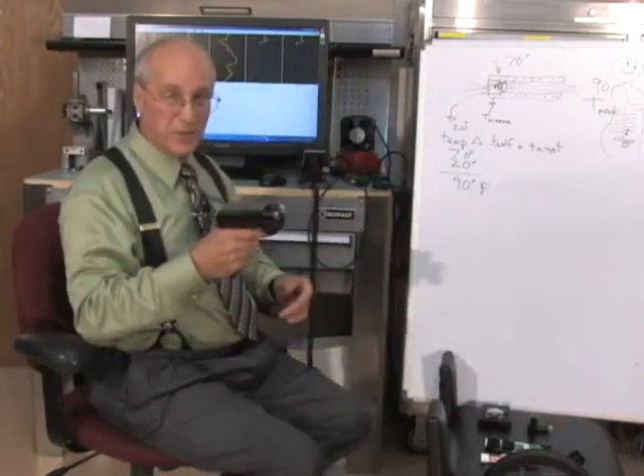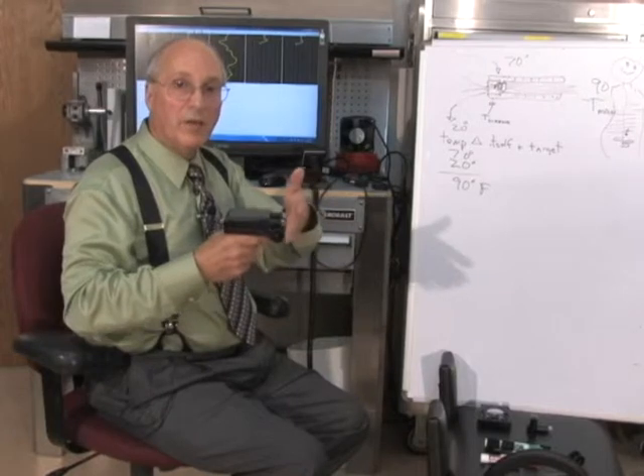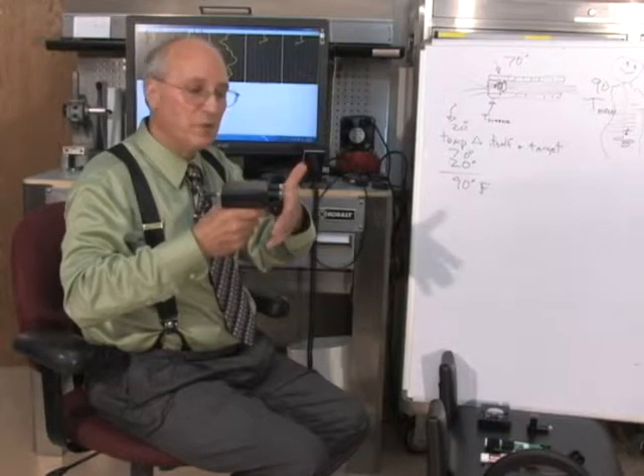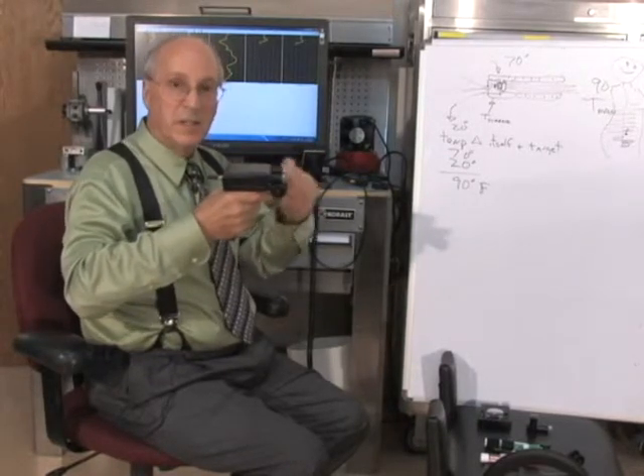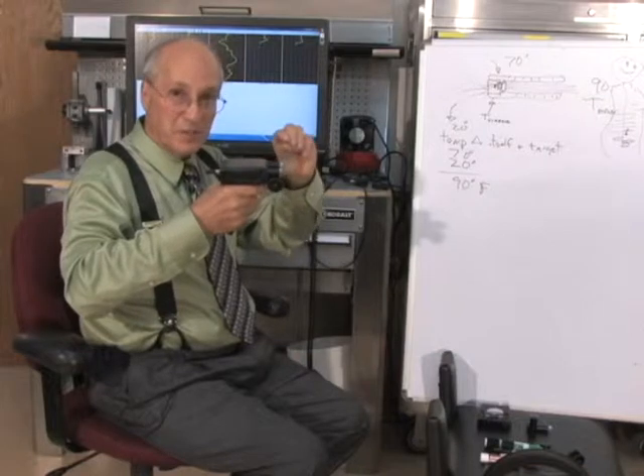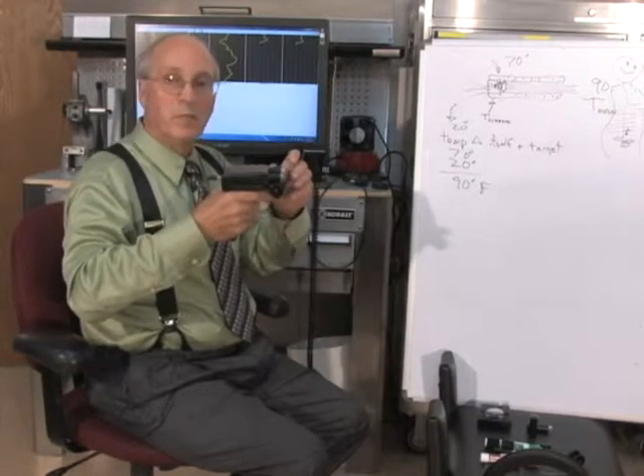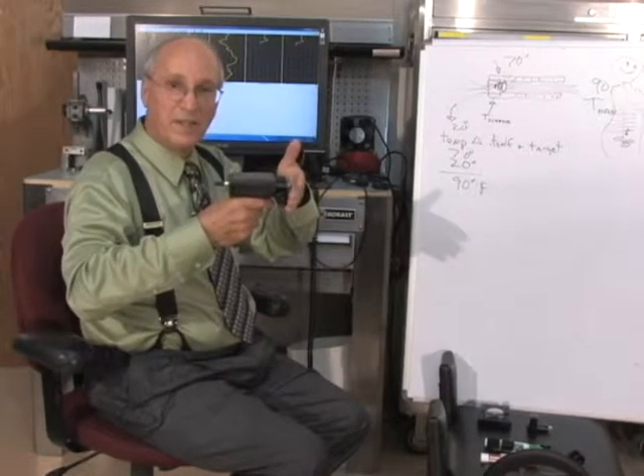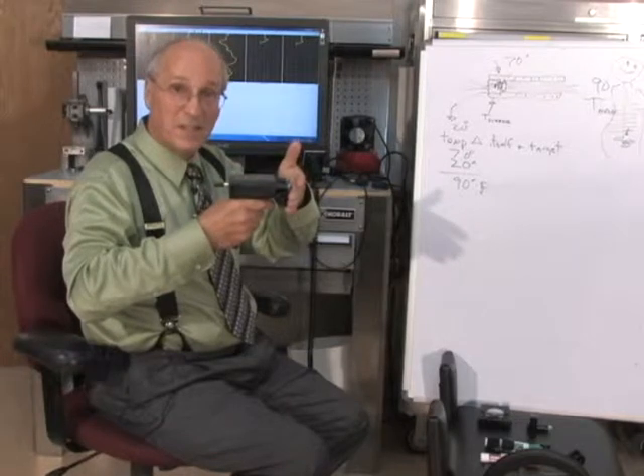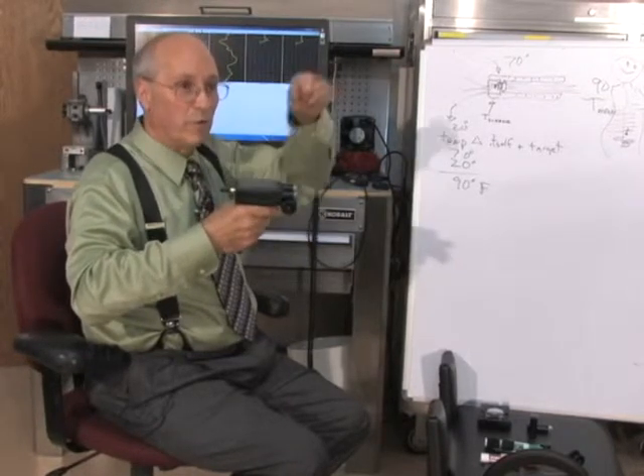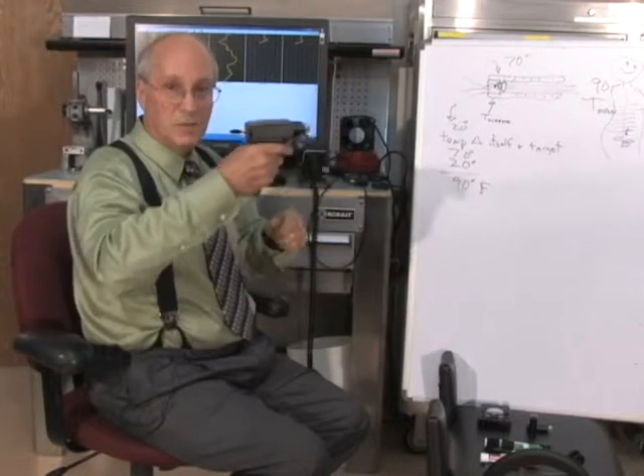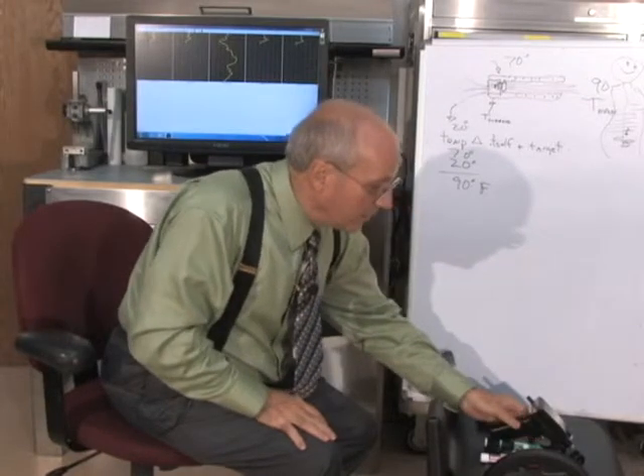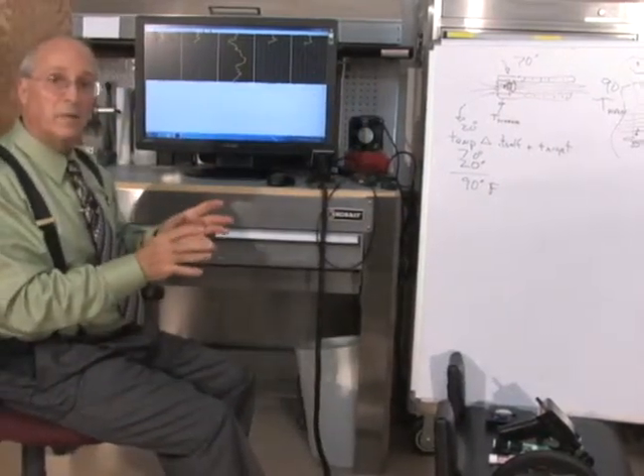When you pull the trigger on the scanner, nothing happens as far as data you're recording until you start to move. As you move, whether slow or fast, data is taken every incremental step as that wheel turns. In the middle of a scan, if you just stop, keep your trigger pulled and hold, no data is taken. So you can talk to the patient, move a bra strap out of the way, and continue on. So just wanted to share what it takes to make an accurate instrument.